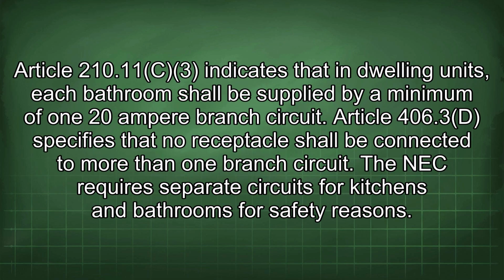Article 210.11(C)(3) indicates that in dwelling units, each bathroom shall be supplied by a minimum of one 20-ampere branch circuit. Article 406.3(D) specifies that no receptacle shall be connected to more than one branch circuit.